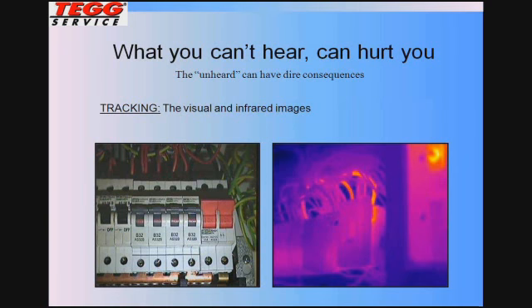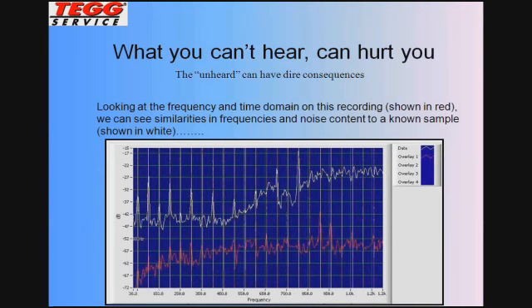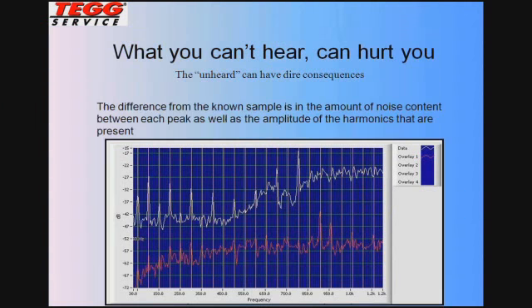In the frequency and time domain, on this slide, I have the recording shown with the red trace and a known sample of tracking in the white trace. Now, the largest difference here is I still have the first few fault frequencies and a lot of frequency content in both recordings. The amplitudes of the frequency faults on the known sample are somewhat higher because the circuit breaker we found was just light tracking. It was early stages. So we didn't have as high of an amplitude on those fault frequencies.